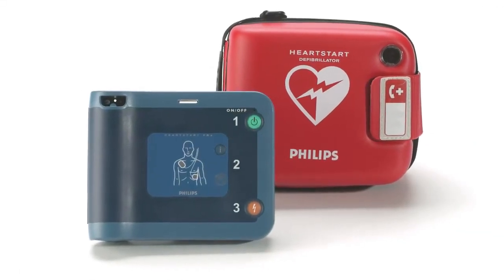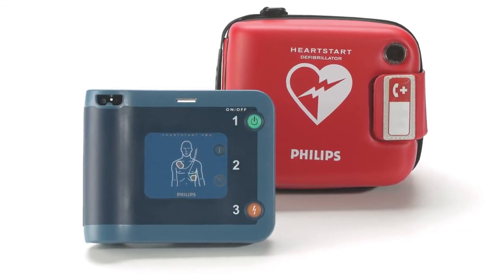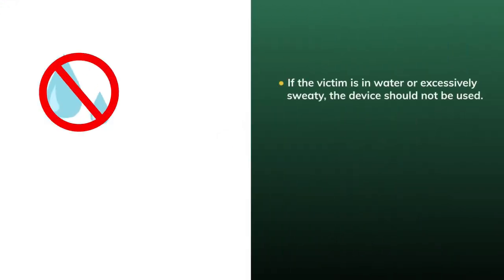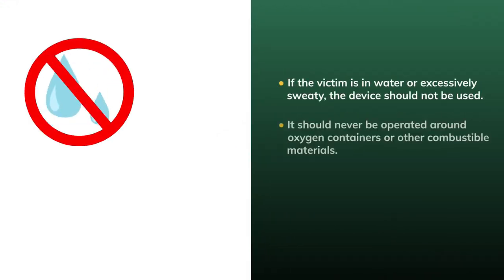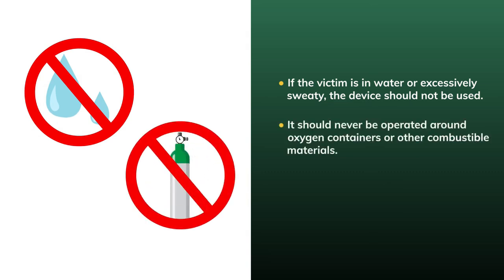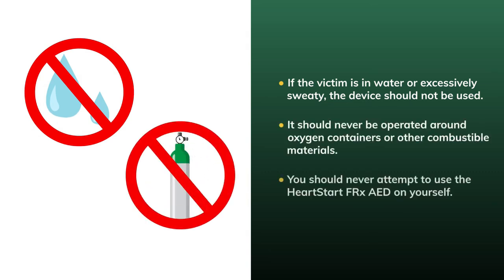There are certain situations where the HeartStart FRx or any automated external defibrillator should never be used. If the victim is in water or excessively sweaty, the device should not be used. It should never be operated around oxygen containers or other combustible materials, and you should never attempt to use the HeartStart FRx AED on yourself.